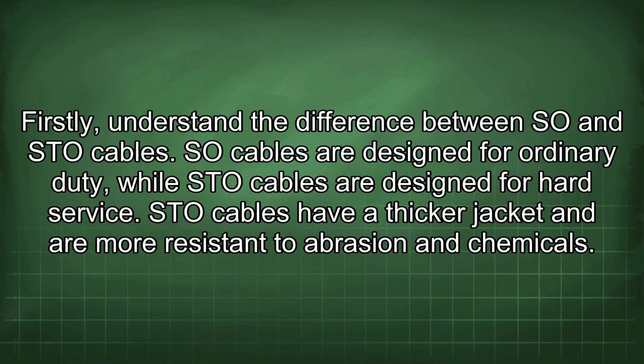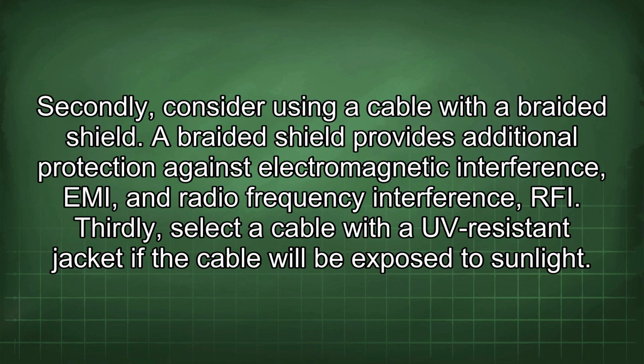Firstly, understand the difference between SO and STO cables. SO cables are designed for ordinary duty, while STO cables are designed for hard service. STO cables have a thicker jacket and are more resistant to abrasion and chemicals. Secondly, consider using a cable with a braided shield. A braided shield provides additional protection against electromagnetic interference (EMI) and radio frequency interference (RFI).